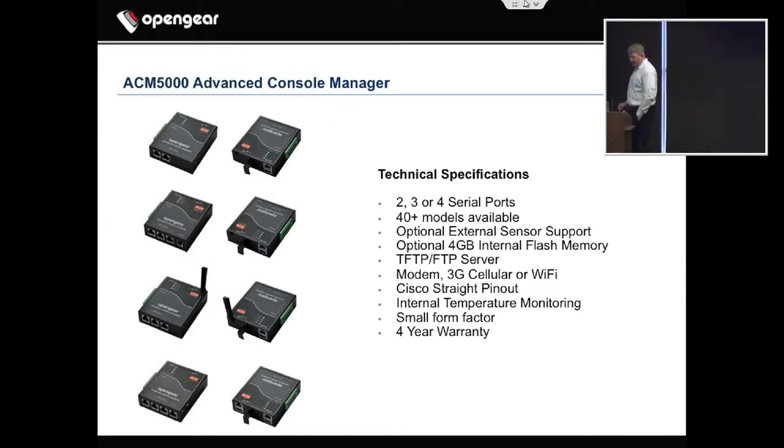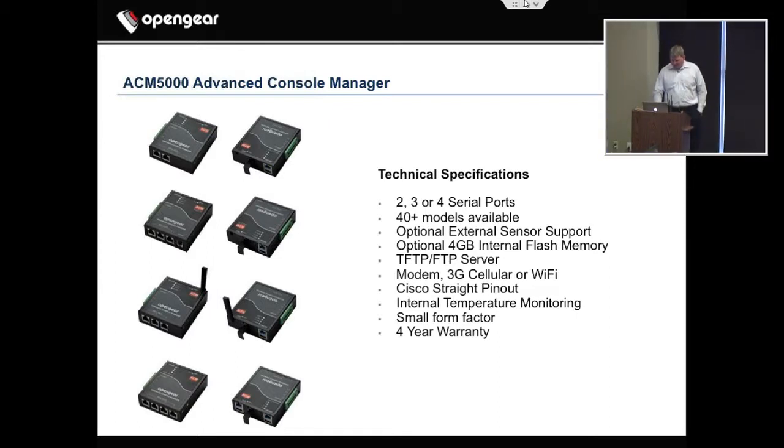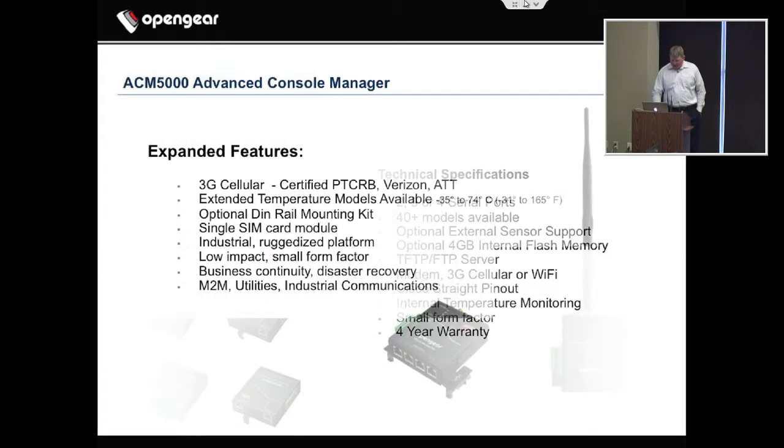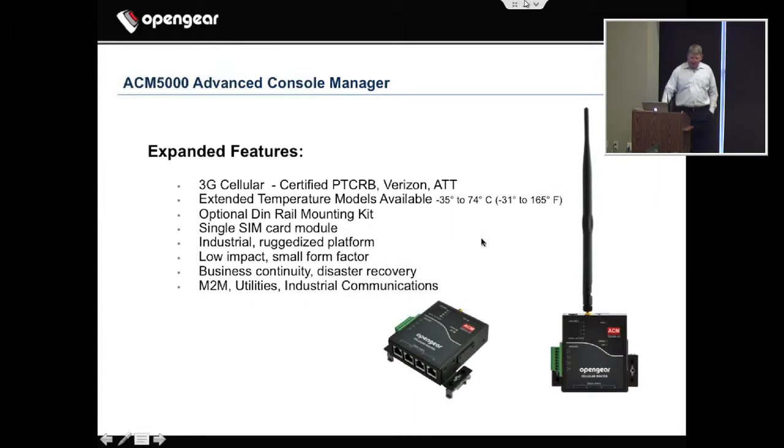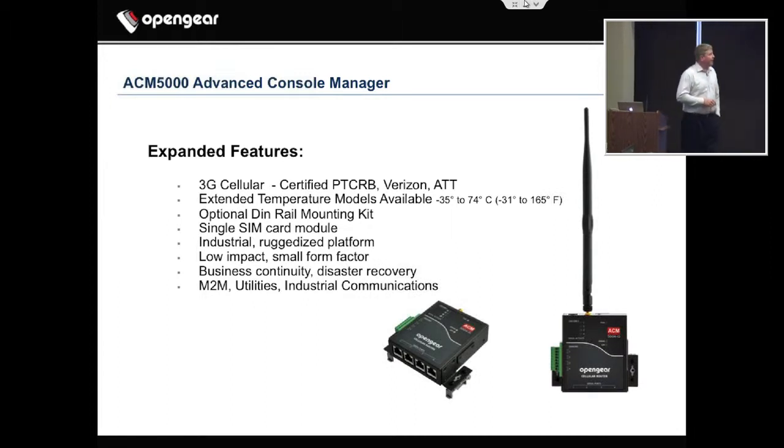We do offer them with environmental sensors, which is this green connector block, which is an additional product model that allows for connectivity to water leak detection, smoke, fire, door contact sensors, and vibration. We do sell all those. It's a normally open, normally closed 5-volt digital I/O. Let's see, we also offer a DIN rail mounting kit. We offer the high temp models up to 165 degree Fahrenheit. So there's non-extended temperature models, and we also have high temp models. The goal is uptime, M2M, industrial communications, and ensuring business continuity.